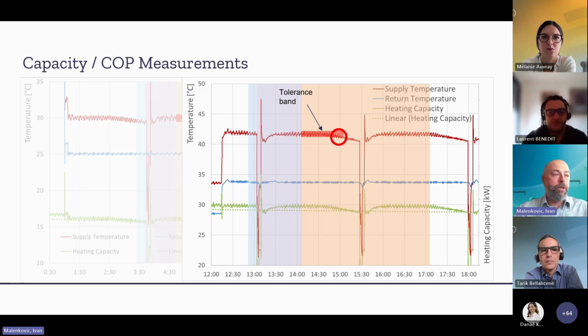However, what can happen is that you have some super cycles induced by the control system, which cannot be seen here, but it can happen. If you are at the test point, let's say air temperature 7 degrees, and the control unit has exactly 7 degrees as the point where the ventilator will change its speed from one to another, it can happen that your ventilator speed is not constant. If you're a little bit below 7 degrees, it will go to a higher speed and so on and so on. So you have some unsteady things going on, which you cannot detect so easily from your measurement, especially if you have automated systems.